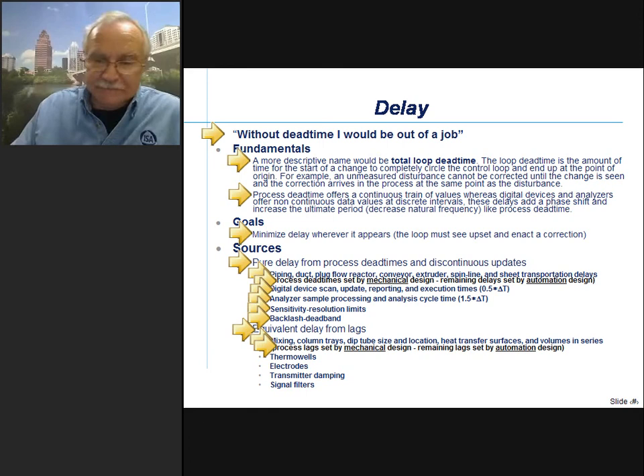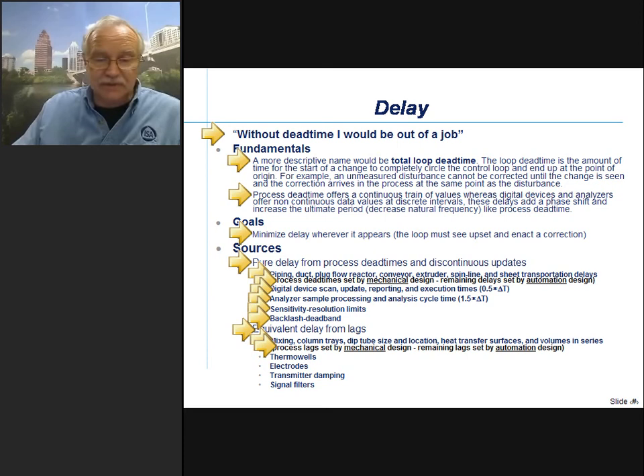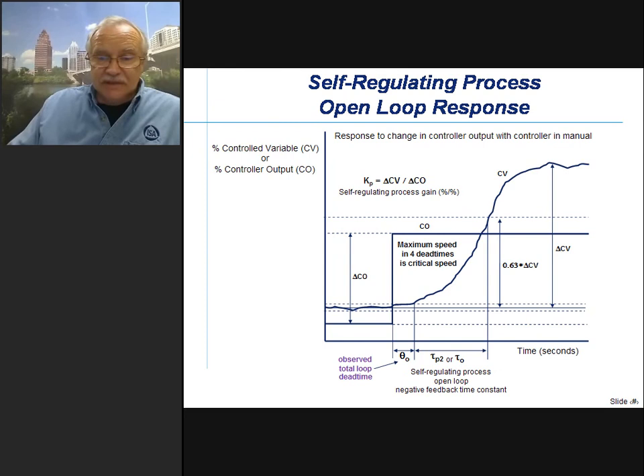Now, the remaining lags are set by the automation design. So you, again, as an automation engineer, have control over a significant source of lags. And again, actually, most of the loops have delay. The largest source of delay is really within your realm of correcting through the automation system design. And so equivalent lags in the automation system design are from thermowells, electrodes, transmitter damping settings, and signal filters.